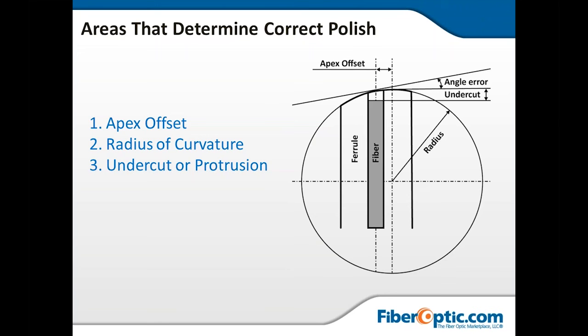Let's look at the radius of curvature, which measures how round the ferrule tip is when it's polished. That radius is usually around 20 millimeters from a theoretical center, and it needs to be uniform. I'll show you in the next slide what the parameters or specs are — the radius of curvature needs to fall into a certain spec to get the desired result.